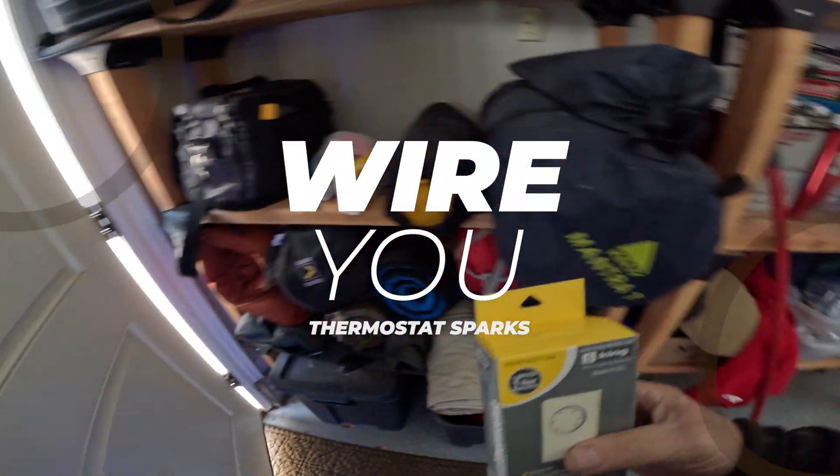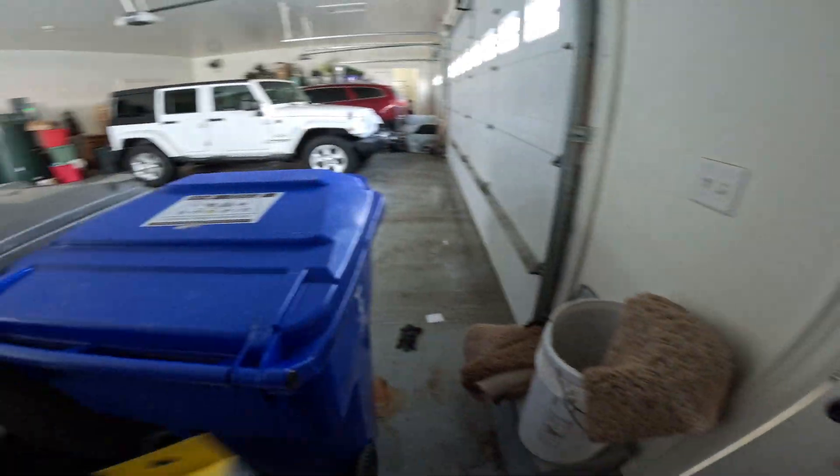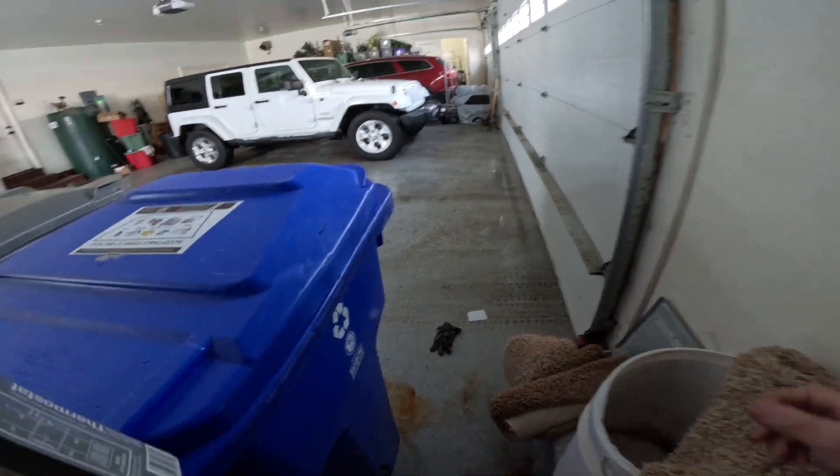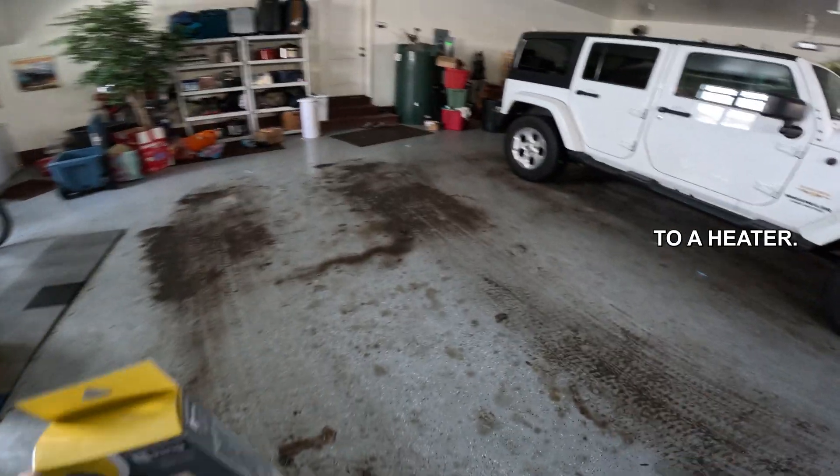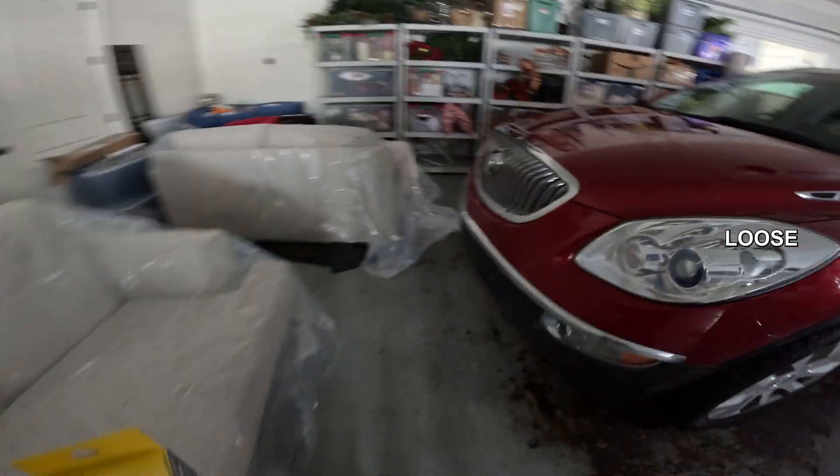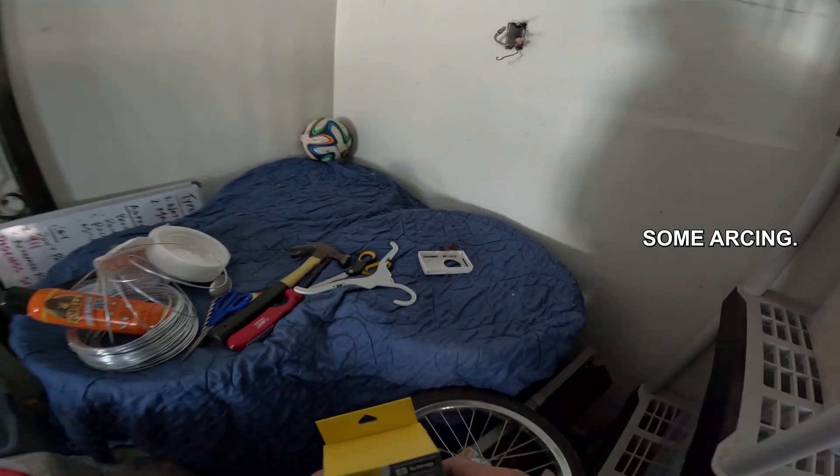I got called to this house because there's sparks coming out of a thermostat and they were also concerned there was sparks coming out to a heater. We came over and pulled off the thermostat and there was a loose connection in the wire nut and that did cause some arcing.